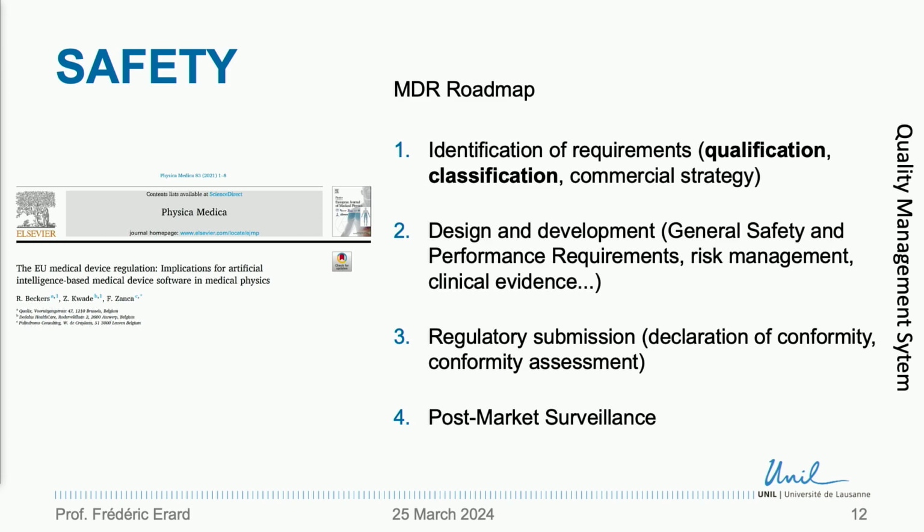And then it's not finished. You need to do post-market surveillance. There are some obligations. You need to make sure you can collect feedback on what happens after you put the device on the market. So I said it's not very different from traditional medical devices. It is the case if we take the European legislation, but you need to take into account that if you talk about machine learning, this implies an autonomous character, constant changes, and then it might actually be a bit difficult and challenging to comply exactly with this regulation today.